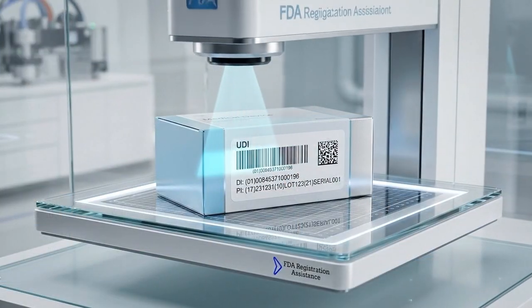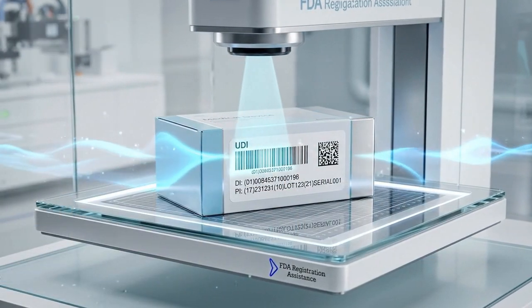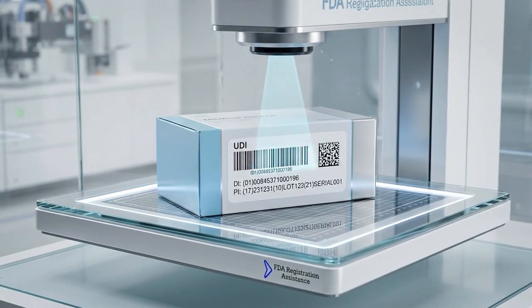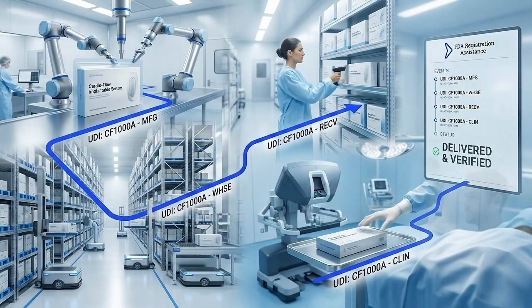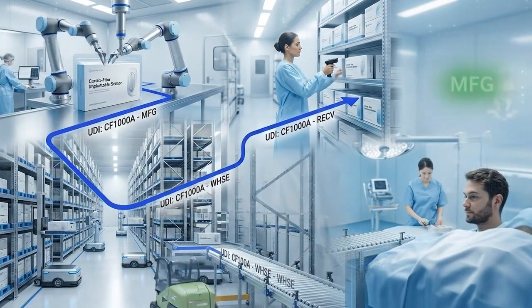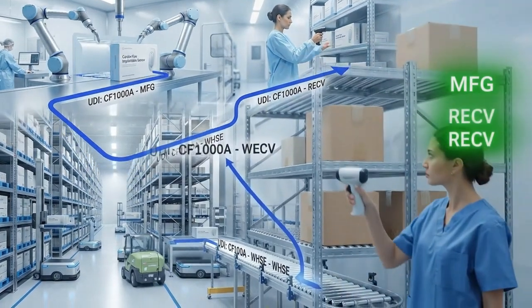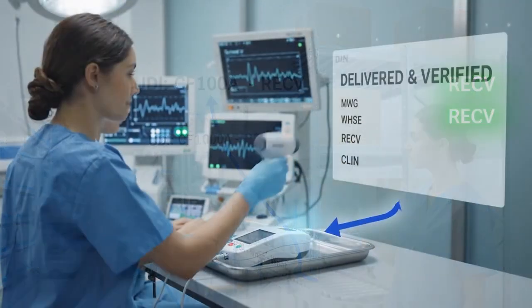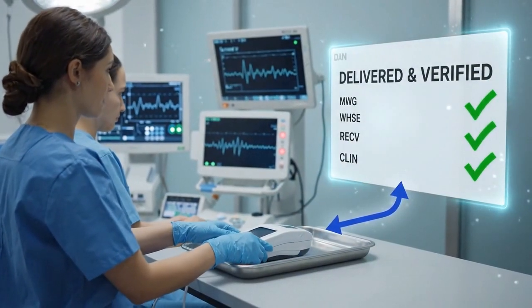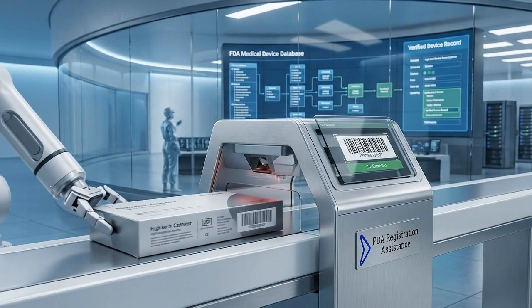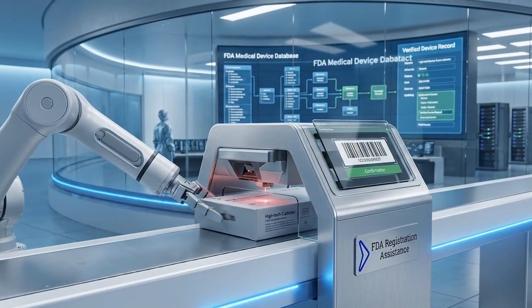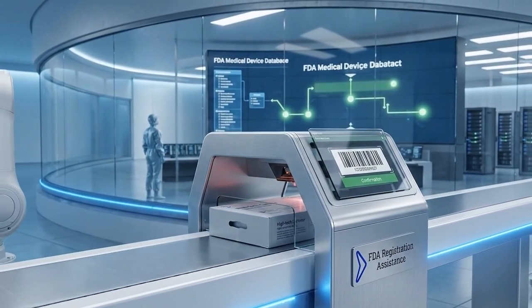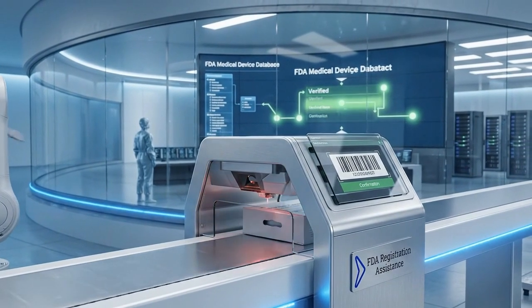One of the most important modern labeling requirements is the Unique Device Identification System, commonly known as UDI. UDI requirements help improve device traceability throughout the healthcare system. Depending on the device classification and regulatory requirements, manufacturers may need to place a UDI on the label and submit related information to FDA databases. UDI compliance has become a major focus area for many medical device manufacturers.